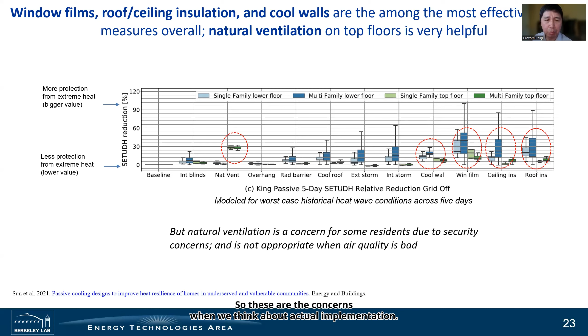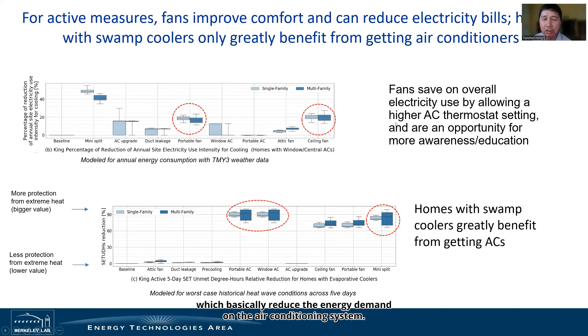We also modeled those active measures, and what we found is that ceiling fans can be efficient in reducing the energy use of the cooling system, because when a fan is running you can have a higher cooling set point, which reduces the energy demand on the air conditioning system.